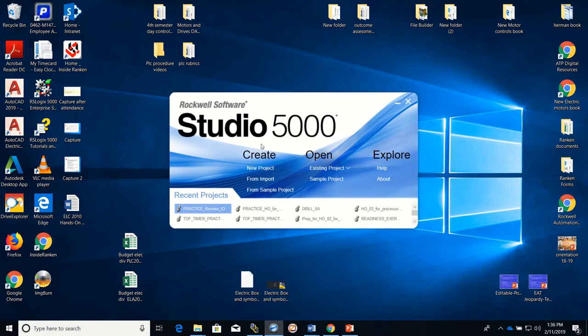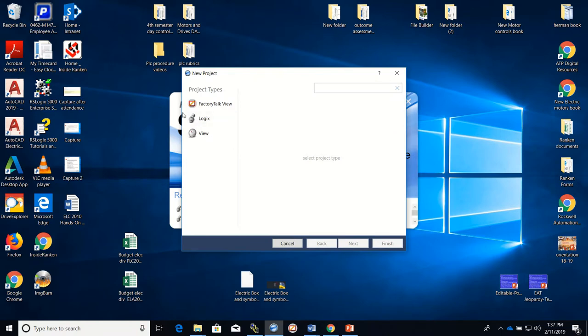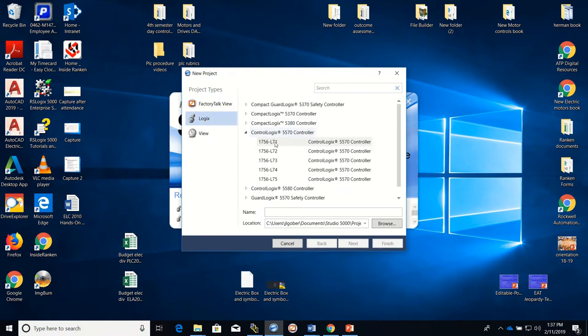This video was made to show you how to set up a remote IO in Studio 5000. To start off, we're going to create a new project. We've done this many times before, so I'll walk through it quickly. I currently have one already made. We'll set up a new project — it's a ControlLogix. I'm using a 1756-L71 processor, and I'm going to name it something that makes sense for the project.